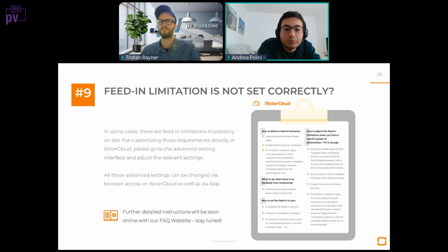The most important parameter is the PV installed power, because the feed-in limitation is based on how many kilowatt peak you have installed, not the AC power of the inverter. So the PV installed power specification is quite important. You need to tell the system how many kilowatt peak you have installed, and also how much of these kilowatt peak you would like to inject into the grid. So please follow the instruction. It also includes special corner cases, like what to do if there is an existing PV inverter in my system, or if you are installing a PV inverter and a hybrid inverter together and want to do feed-in limitation. All of this is included in the guide.